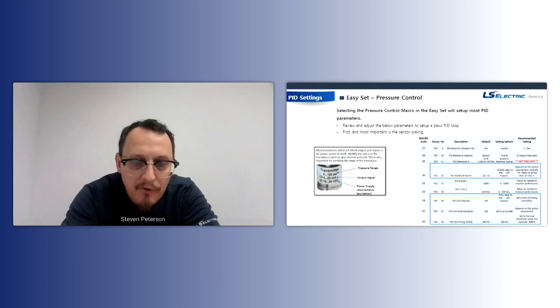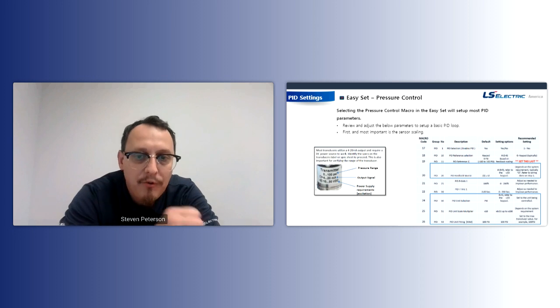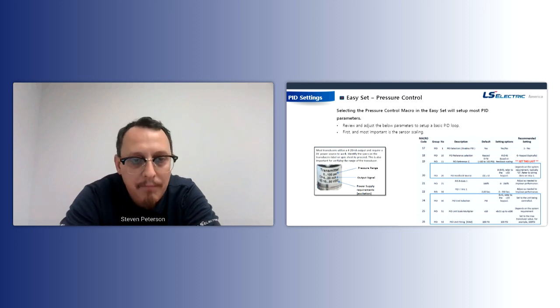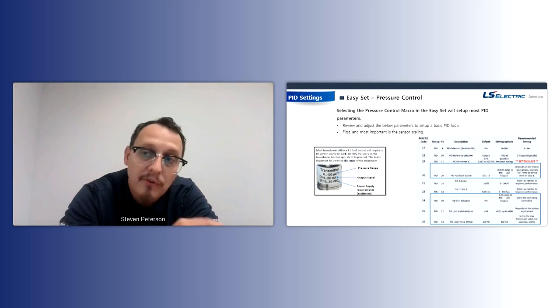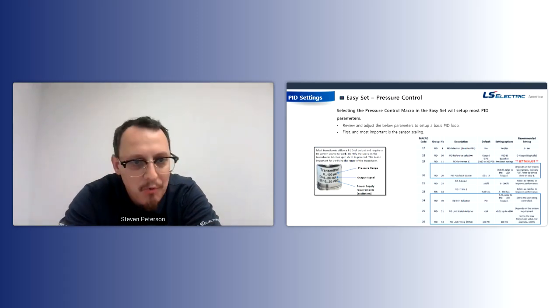So what you're generally going to be doing is reviewing these parameters here. And the first thing we recommend setting is your pressure transducer scale. That's an important thing because if your scaling is not right, everything else is going to be wrong.